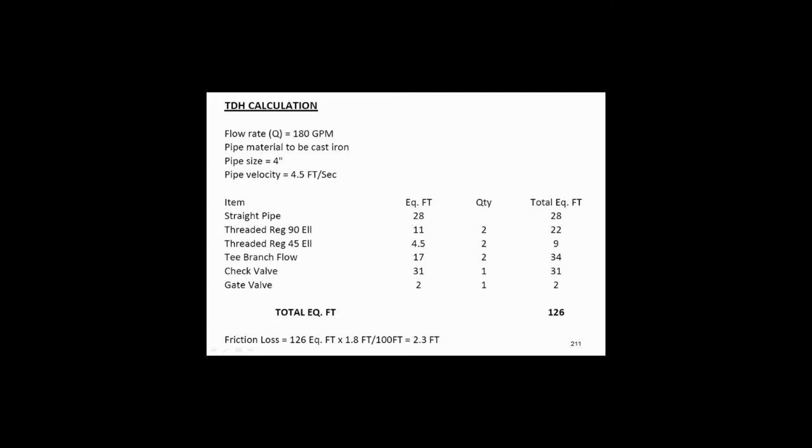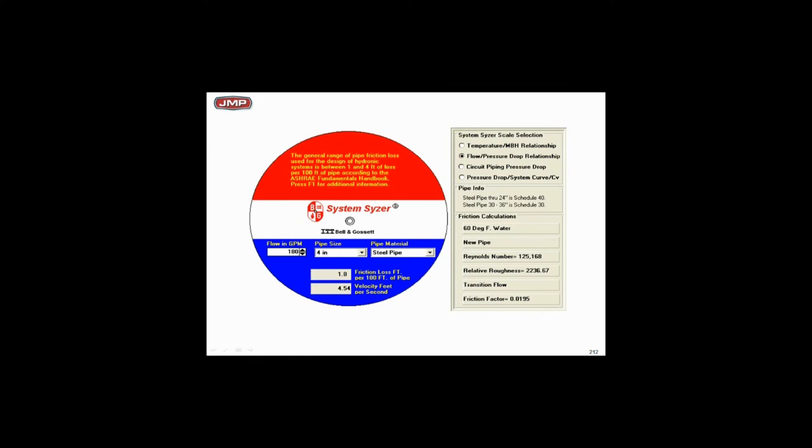And my friction loss, when you see from the system sizer in a minute, at 180 GPM, four-inch pipe, is 2.3 feet total. That's my friction loss. So if I go to my system sizer, here's a quick snapshot, 180 GPM, four-inch pipe, you'll see the friction loss is 1.8 feet per 100 feet of pipe. There's my velocity about four and a half feet per second. That's where I've got my numbers from.